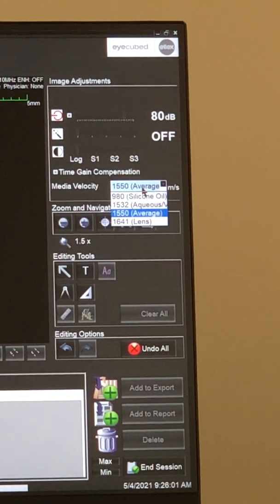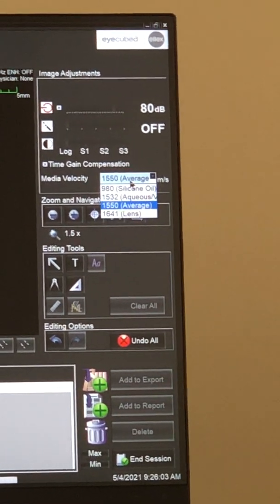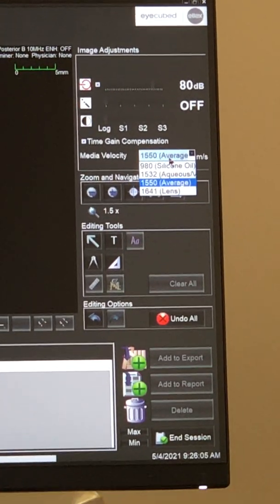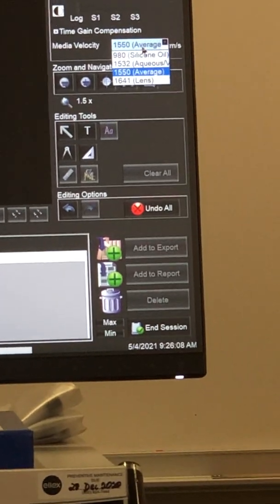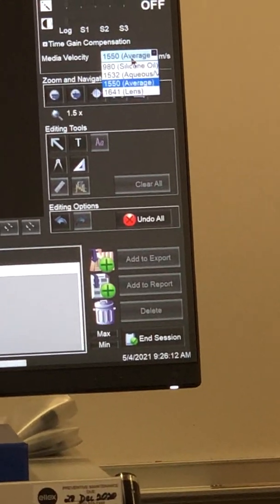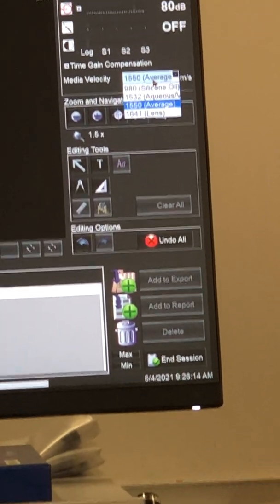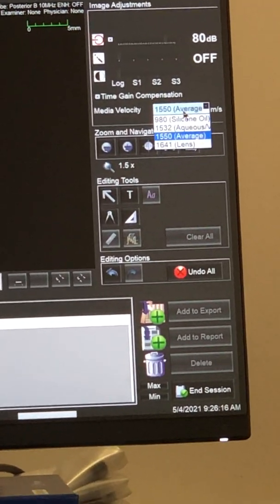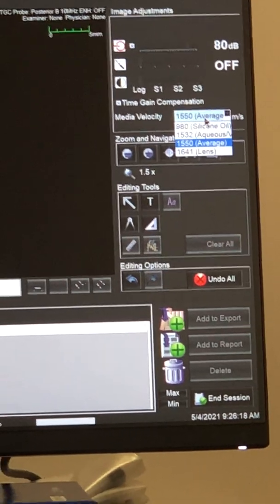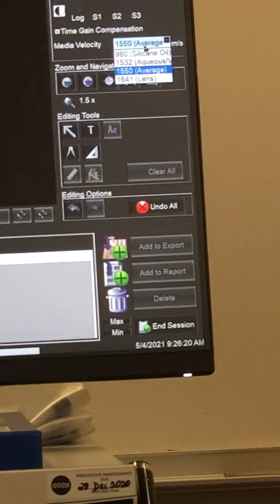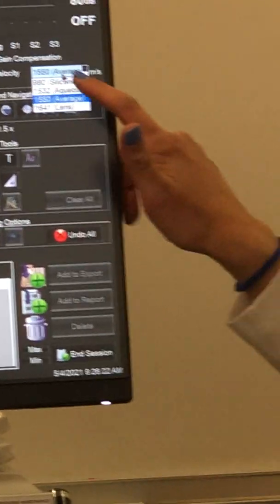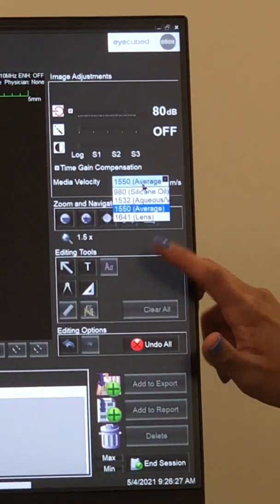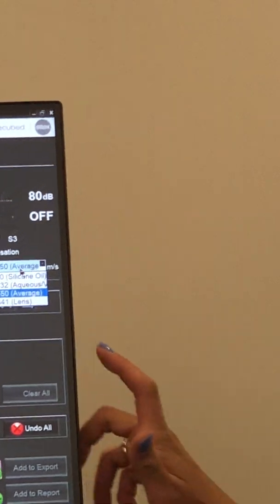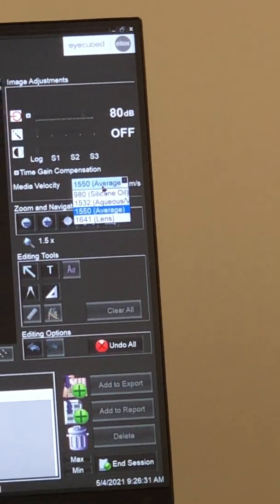Okay, so this is important if you're scanning an eye that has a silicone-filled globe and you want to do some measurements on it. This is also really useful in what's called a B biometry. So if you do an immersion B scan, say you can't get an A scan or you're getting really erroneous A scan measurements, you can do what's called an immersion B scan. And you can measure each chamber of the eye using the correct velocity, and it will automatically adjust the measurement for you. Depending on the chamber.